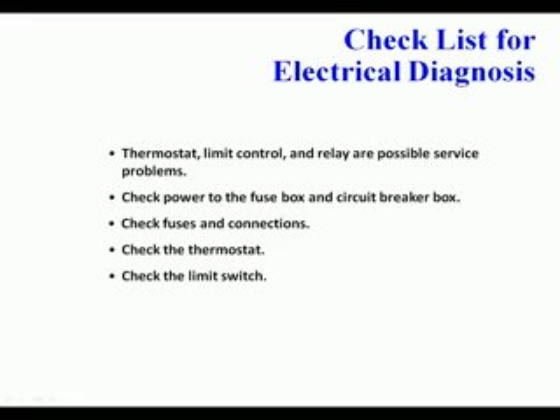If the blower turns on and off, and the heater strips heat and cool as the blower runs and stops, the thermostat is short cycling. The anticipator rating may be set too high. The limit control may be opening and closing. You may have an incorrect low voltage, and the motor overload may be opening and closing.